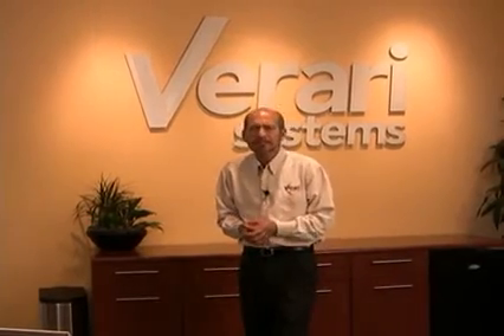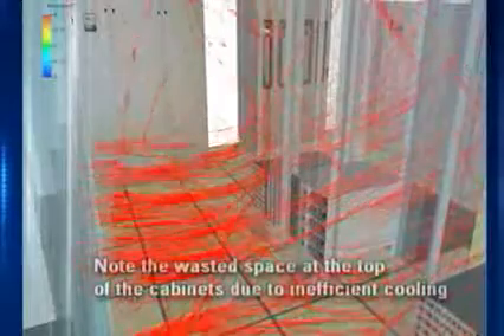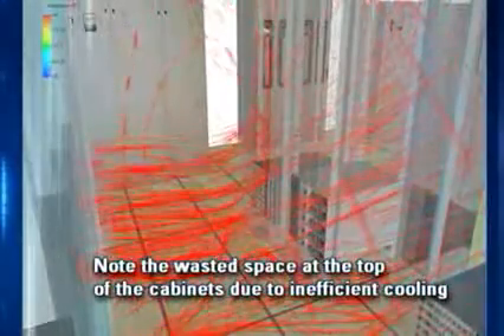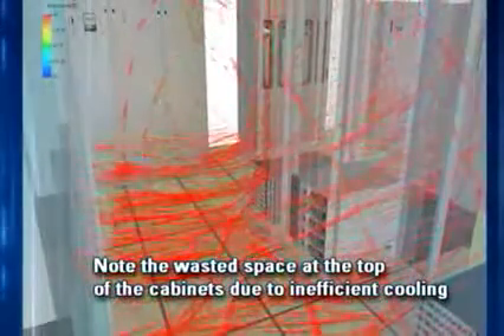And we started seeing this in our competitors' products as people would put a high density platform like a blade architecture, but then only put 2 of them into a rack. Why? Because they couldn't cool them from within 1 floor tile. We set out to fix this problem. People didn't want to change their density. They still wanted to be as dense as possible. So we looked at where could we get more air from. If we increased the number of floor tiles in front of the rack, that wasn't going to help us because that would decrease our density.